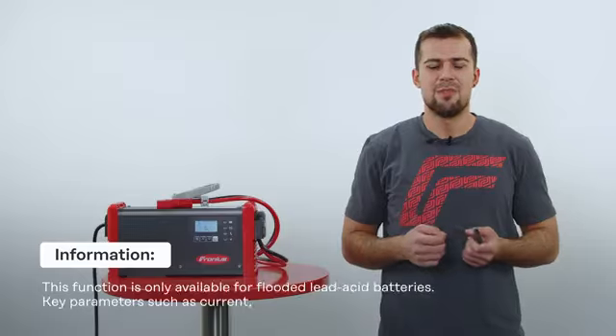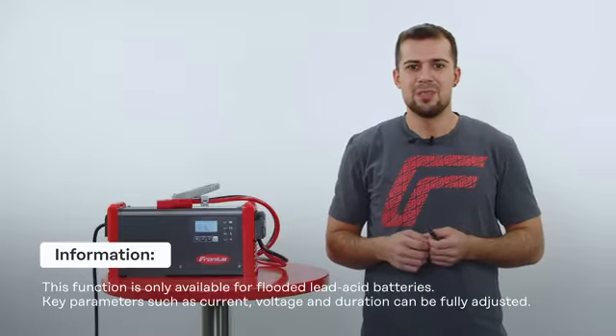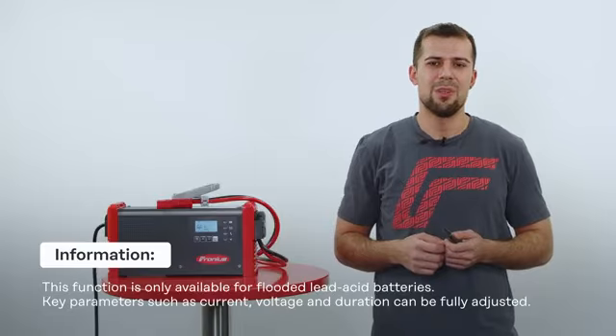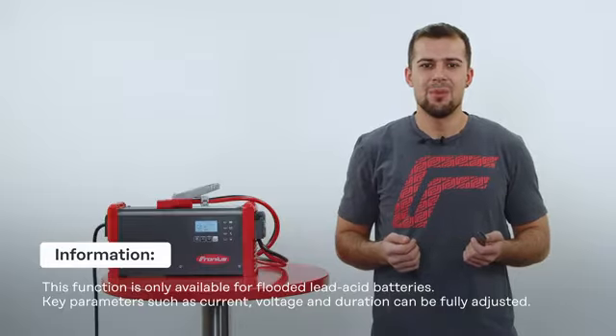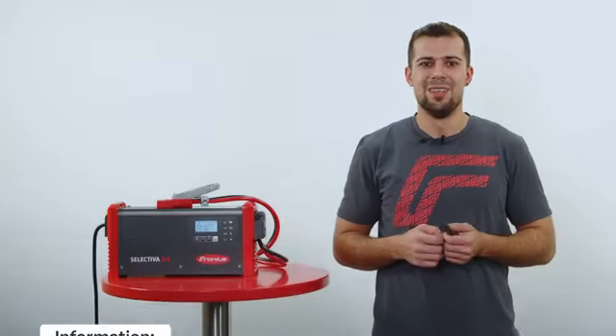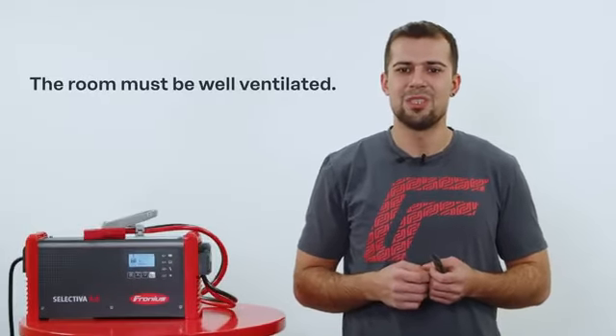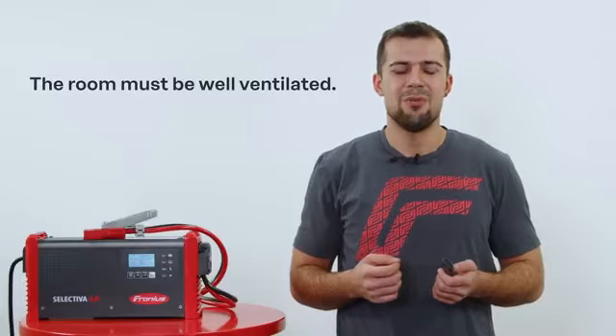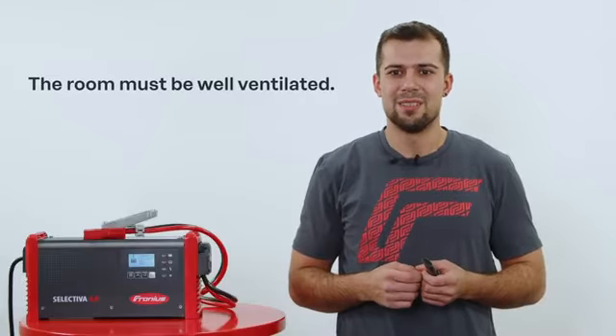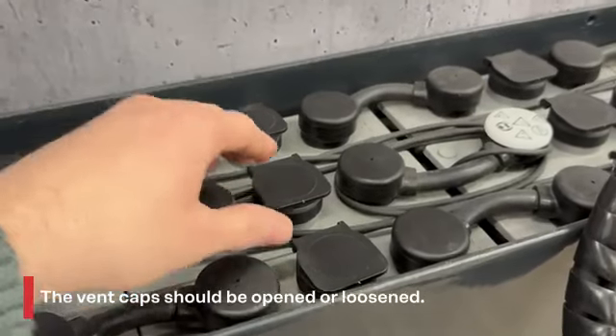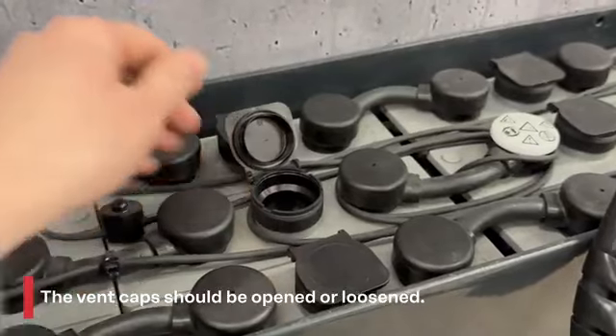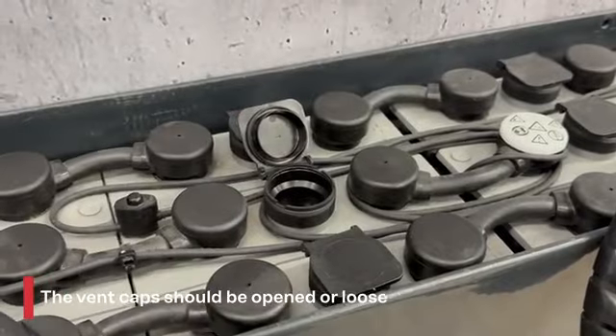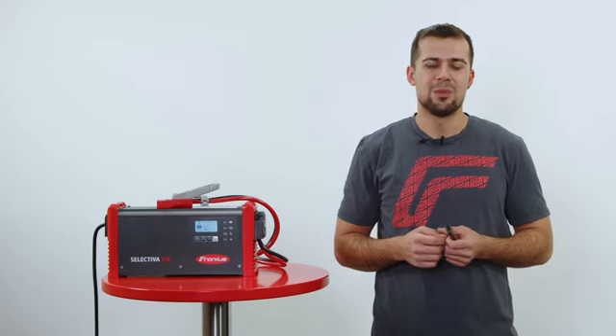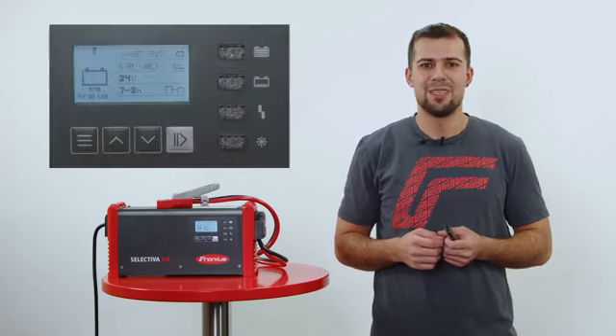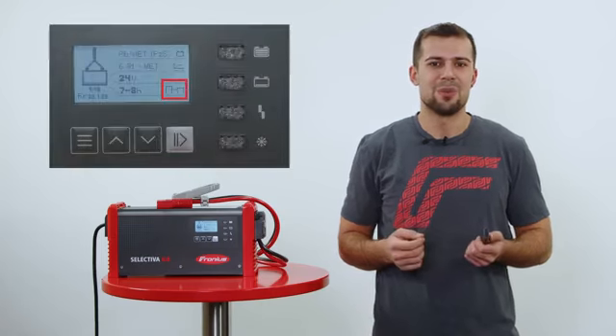This function is only available for flooded lead-acid batteries. Key parameters such as current, voltage and duration time can be fully adjusted. During controlled overcharging, the battery produces gas. Therefore, the room must be well ventilated, and the vent caps should be open or loosened. The current status of the equalization charge is always indicated by an icon on the home screen.